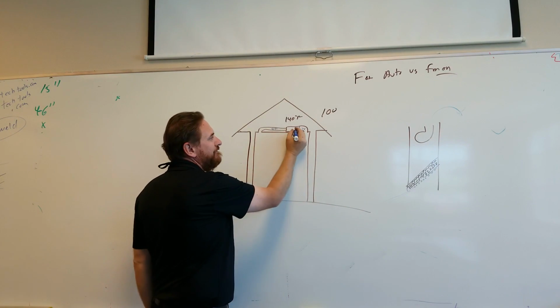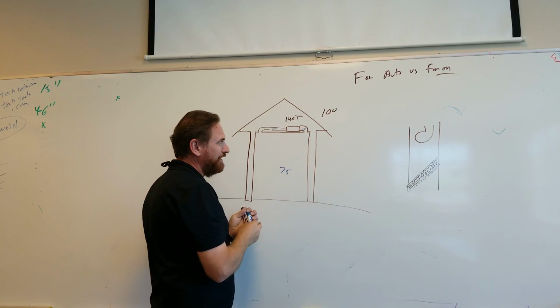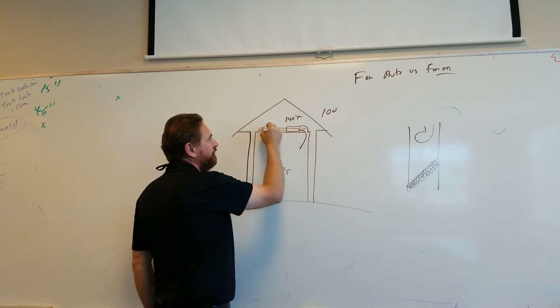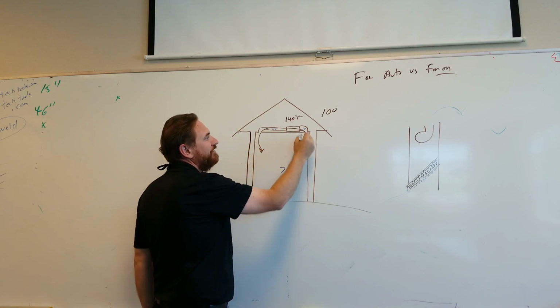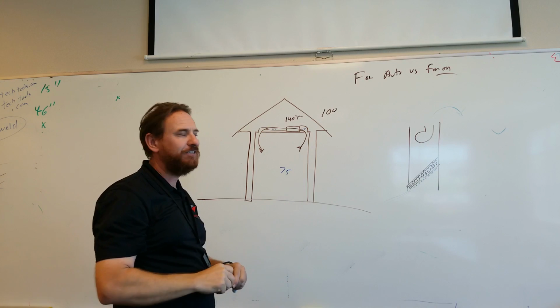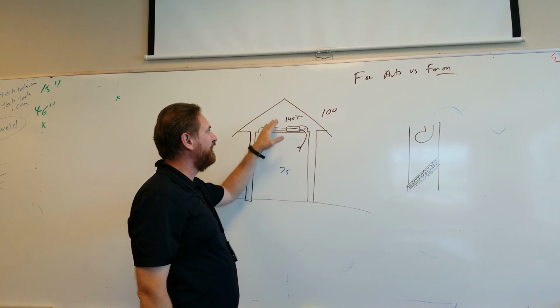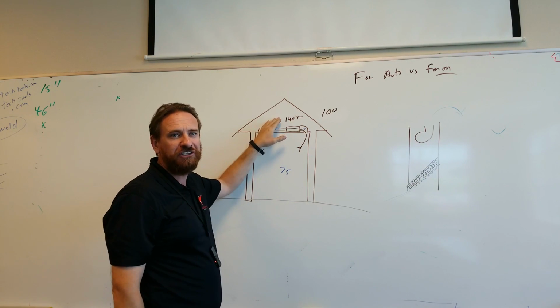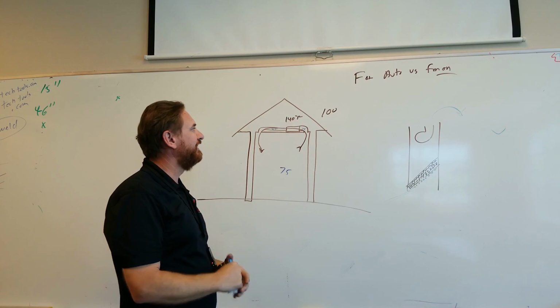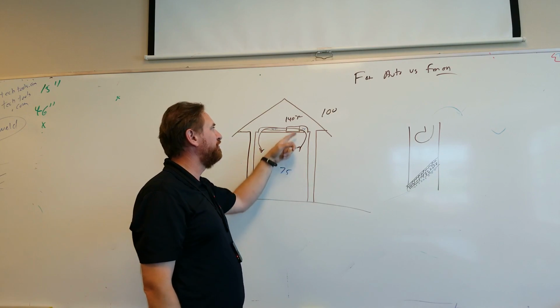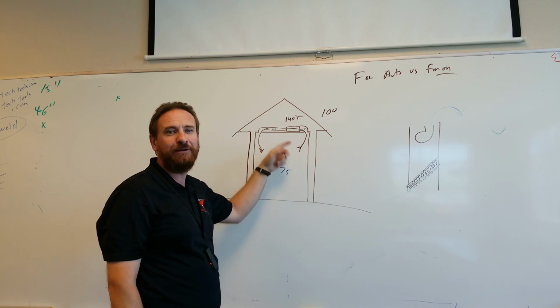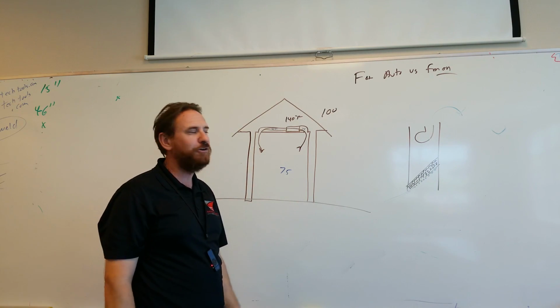Now if I leave that fan in the on position and I'm moving air through this unit, through the attic all the time, non-stop, keeping that air moving through that unit, then there's more air touching more of that hotter temperature attic all the time. So one of the theories is by leaving that fan in the on position, you're actually heating the air in the house up. Plus also if you look at the heat of the motor.